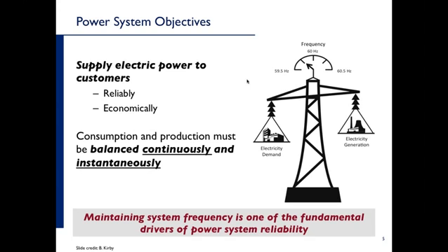There is the possibility that there's a slight difference between them, and if that happens, you can see in this diagram on the right, we have a stylized transmission tower that looks like a balancing weight in effect. In this particular example, we have electricity generation on the right, which is a little bit less than demand on the left. And so that sort of pulls the scale, if you will. And in this example, we see the system is deviating from the nominal frequency. In this case, the nominal frequency is 60 hertz.